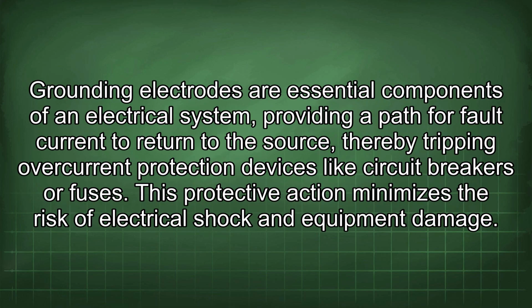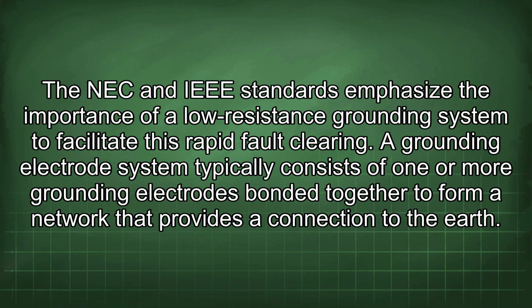Grounding electrodes are essential components of an electrical system, providing a path for fault current to return to the source, thereby tripping overcurrent protection devices like circuit breakers or fuses. This protective action minimizes the risk of electrical shock and equipment damage. The NEC and IEEE standards emphasize the importance of a low-resistance grounding system to facilitate this rapid fault clearing.